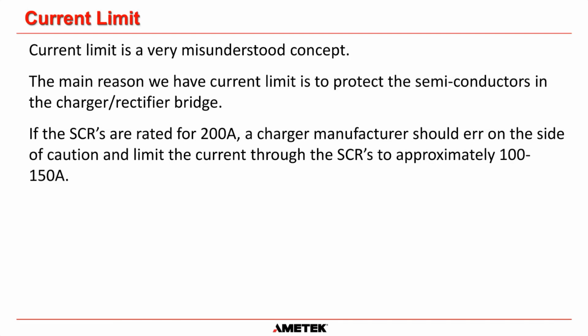So let's say we had a battery charger and the spec for that charger called out an SCR that was rated at 200 amps. Then the charger manufacturer is going to err on the side of caution and probably limit the current through those SCRs to approximately 100 amps, maybe 150, depending on the manufacturer. Okay, they don't want to exceed the rating of the SCRs because they may blow up or get damaged. So that is the reason we have originally why current limit was created, because we can create a 50 amp charger, a 100 amp charger, 200 amp charger, a 500 amp charger that use the same control boards and everything, and all we do is change the SCRs and the transformers to rate them up or rate them down.